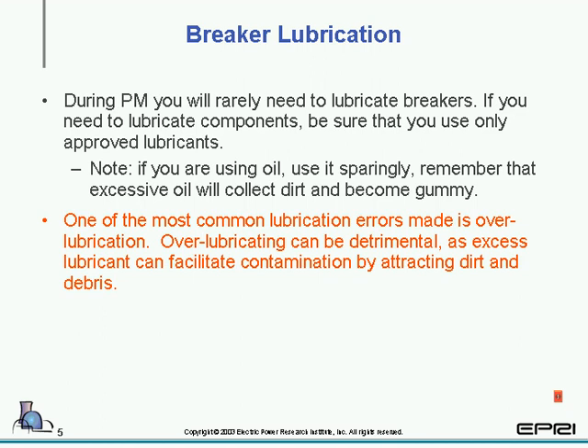Breaker lubrication. During PMs, you rarely need to lubricate any parts on the breakers except for the primary disconnects. And if some manufacturers use oil, you want to use it sparingly. You also want to keep in mind, especially if you're taking a test, one of the most common lubrication errors made is over-lubrication. Over-lubricating can be detrimental. Excess lubrication is basically a magnet for contamination. So that's one of the reasons why you don't want to over-lubricate.